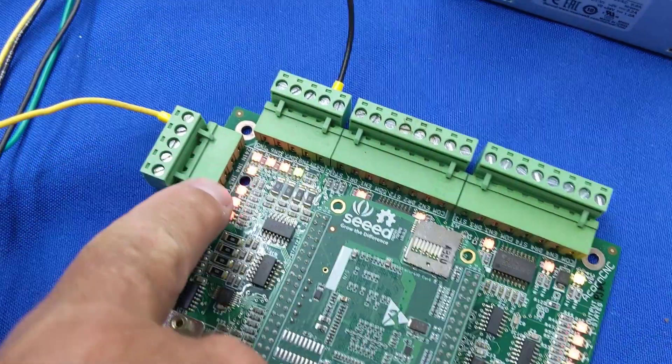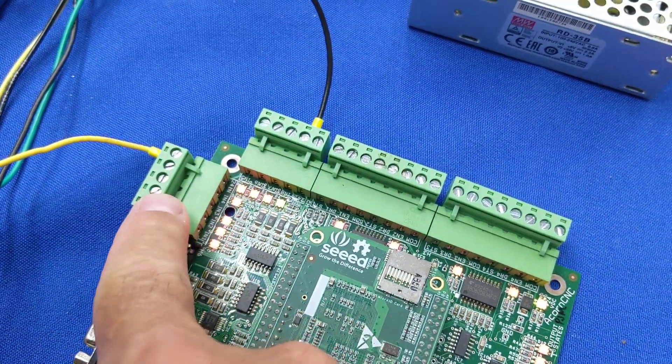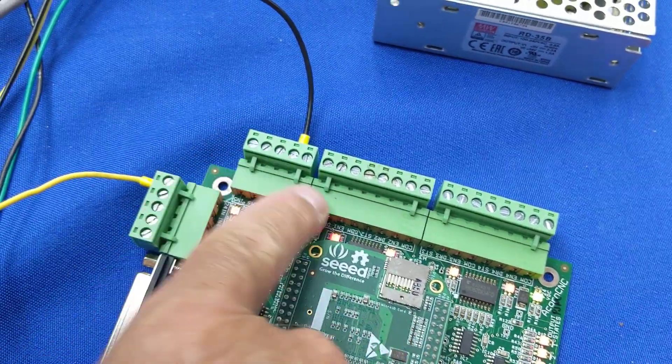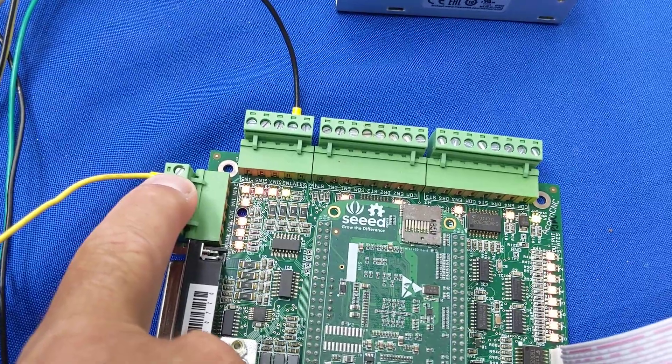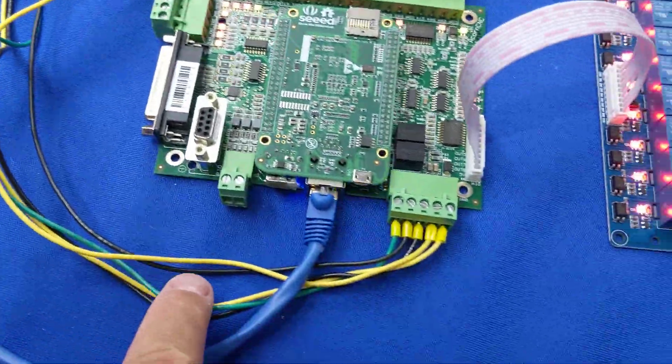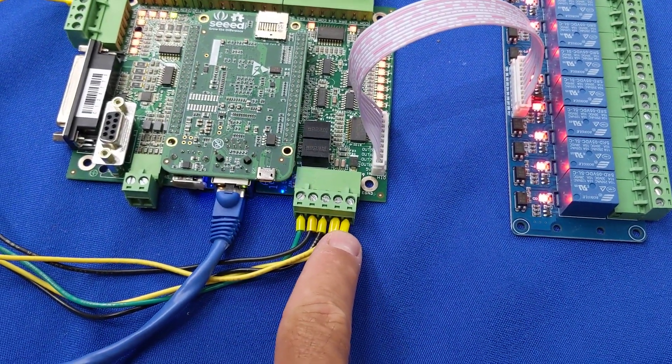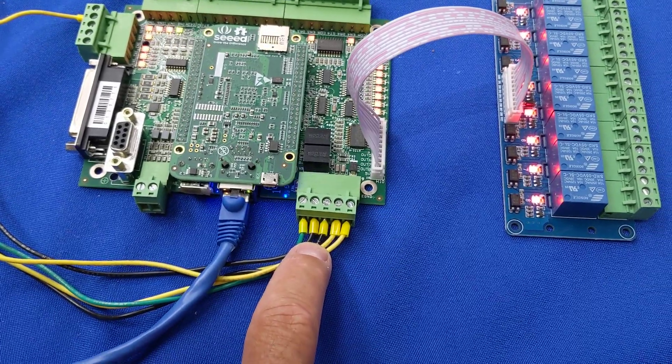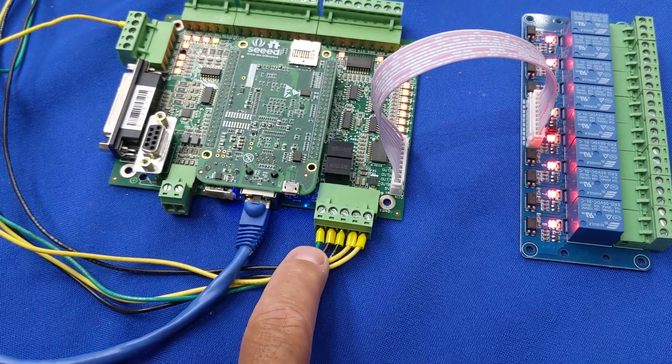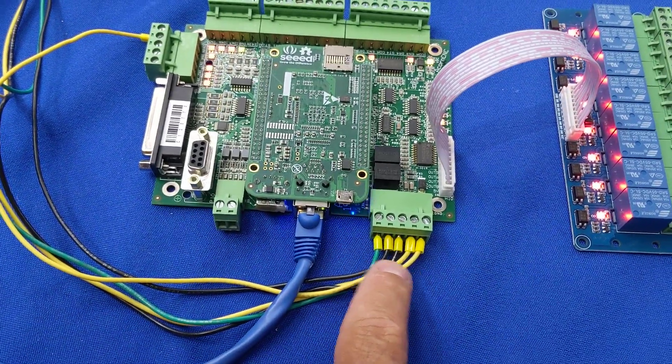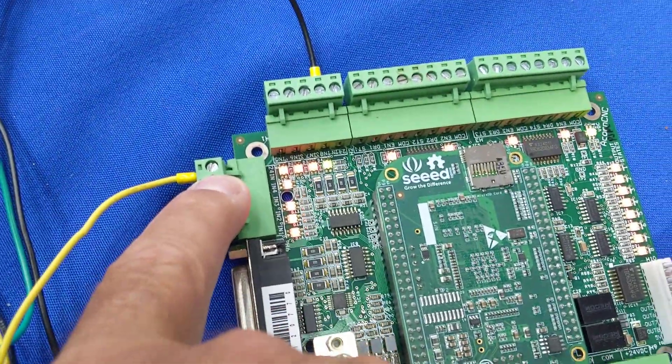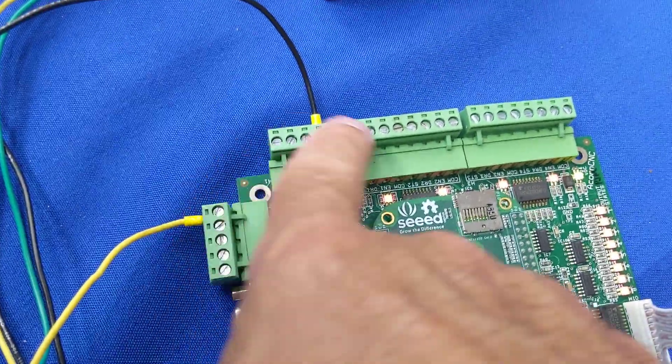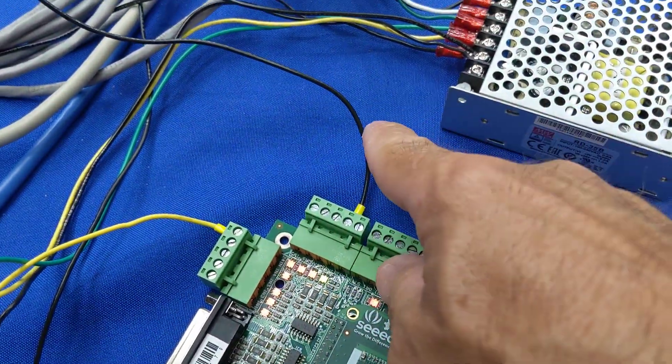On the upper left hand side of the ACORN board we have the input headers. So these are inputs 1 through 4, 5 through 8 on these two headers. There's also a 24 volt input here as well which I have wired back to 24 volts. So yellow is 24 volt positive, black is 24 volt common or 24 volt negative, and green is ground. So I've got a little wire, a jumper, going from 24 volt positive over here to the 24 volt positive terminal. Once you do that, that sets up the inputs ready to go to close the circuit.